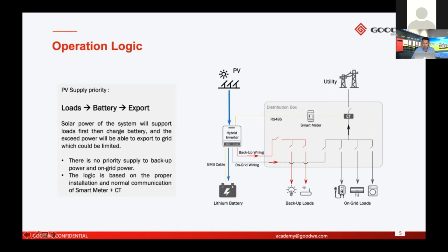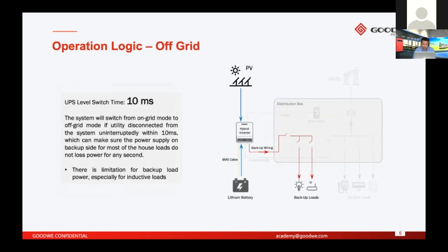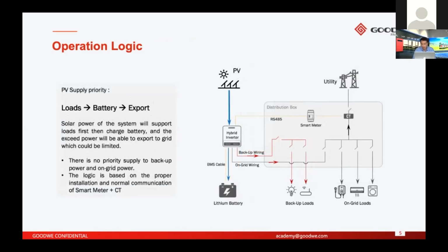The other logic is if the load power is big. For example, if the PV power is low and the load power is high, how does the load consume power from PV, battery and grid? The priority is PV first, then battery, then grid. It means if the load power is high, the PV production will do its best to support the loads. Then the rest will be supplied by the lithium batteries. If the lithium battery is still not enough, then the rest of the power will be drawn from the grid. These are the two basic logics.